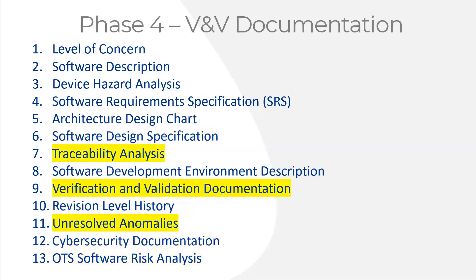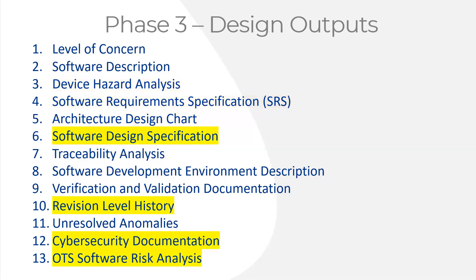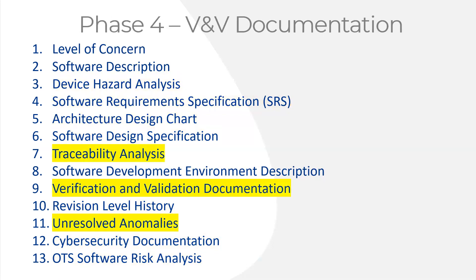Once you've reached the final version, you take all documentation from every unit test and integration test — both passed and failed — and summarize it in your verification and validation documentation. There will probably still be a few unresolved anomalies. For software, if it gives an error message or won't compile, that may be acceptable. But if it compiles and gives a wrong answer in a diagnostic software application, that's an unresolved anomaly that would not be acceptable for release. The FDA also wants a traceability analysis linking all the way back through design inputs — hazard analysis, SRS, and architecture design chart — through design outputs including software design specification and risk analysis — to the verification and validation reports for unit tests, integration tests, and final system validation.